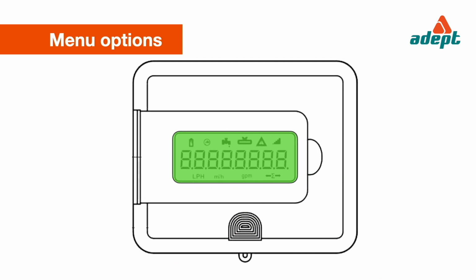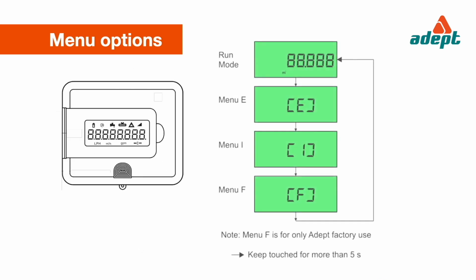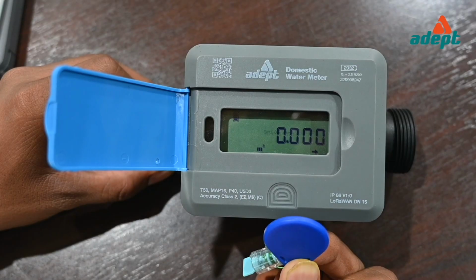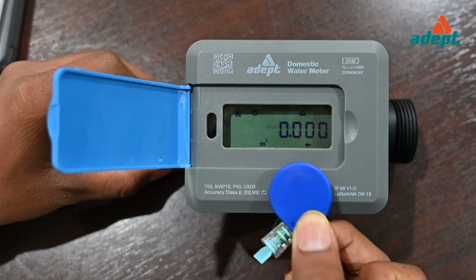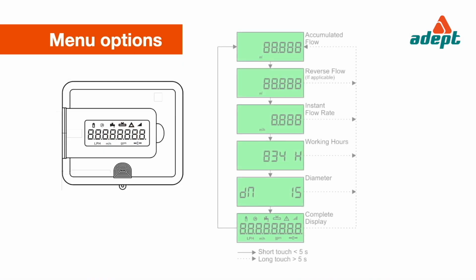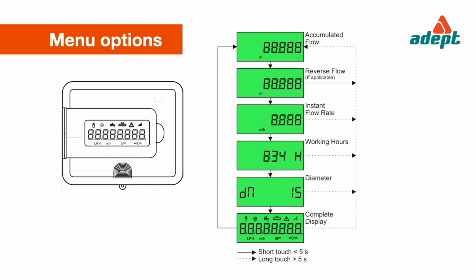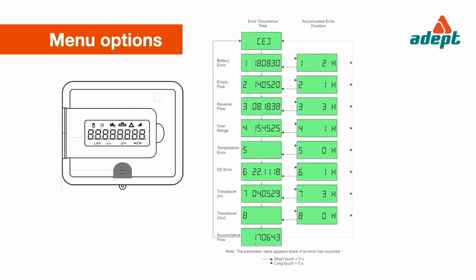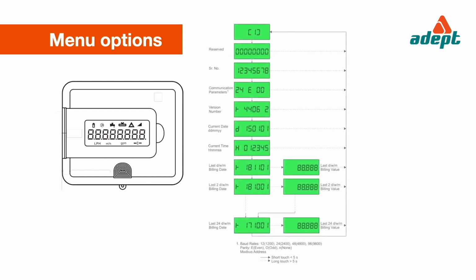Menu options. Operate the switch to move to menu E. Repeat the switch operation to sequentially move from one menu to the next. Run mode. Operate the switch to view the measurement data, working hours, meter size, and to test the display. Error E menu. Operate the switch to check the error information. Information I menu. Operate the switch to view meter details, communication parameters, current date and time, and also the billing history of the last 24 days, weeks, months.